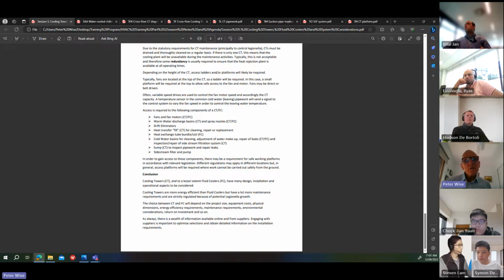As long as, I mean, Legionella is going to take some time to grow, so it's not going to happen instantly. So as long as you're maintaining some flow through all those components on a regular basis, you should be okay. And if the chemical treatment is done correctly, which it has to be, then you're killing off any bacteria anyway. But I suppose dead legs are more common in a small piece of pipe that sometimes doesn't get much flow.